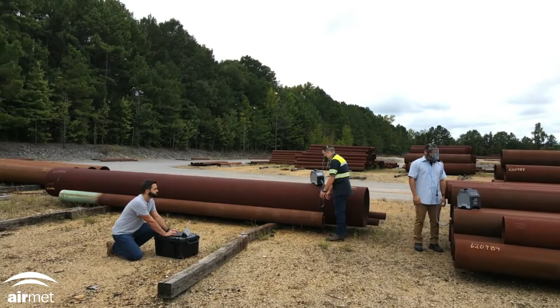The next thing is speed of testing. It's important to remember that speed is not just the protocol of fit testing. Speed of testing is also setup time. You can set up your QuantiFit 2 and go through a full daily verification in under 2 minutes, when other technologies require multiple things to go through to check for filters, to check for calibration setup, and all of those requirements that I just mentioned about room and all the other environments that you have to set up. With QuantiFit 2, we eliminate all of that: full setup and daily verification in under 2 minutes.